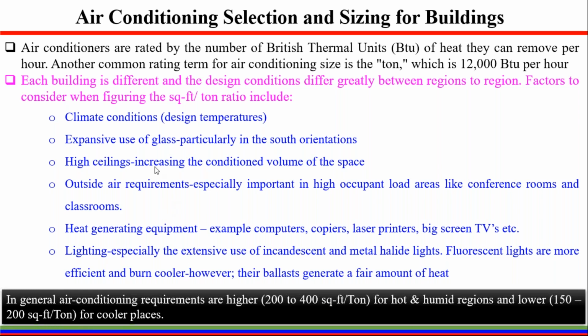When selecting air conditioning, the criteria for each building is different, and design conditions can differ greatly from region to region. But the factors that should be considered when buying air conditioning include the climatic conditions. In which climatic conditions are you buying the air conditioning? Is it very hot and humid, or a little bit cooler? Extensive usage of glass, particularly in the south orientations, because in the northern hemisphere the sun always moves in the southern direction. So we have to make sure that the southern part of the building has the least windows. Ceiling height, how much? Because if you increase the ceiling height, the total area that should be cooled can increase.